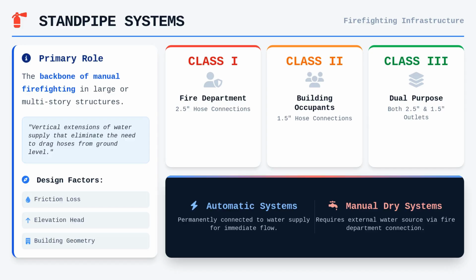These systems must also be classified by their water supply status, ranging from automatic systems, which are permanently connected to a water supply capable of delivering the required flow, to manual dry systems, which require an external water source to be coupled to the fire department connection. Designing these networks requires careful accounting for friction loss, elevation head, and the inherent variability of building geometry.